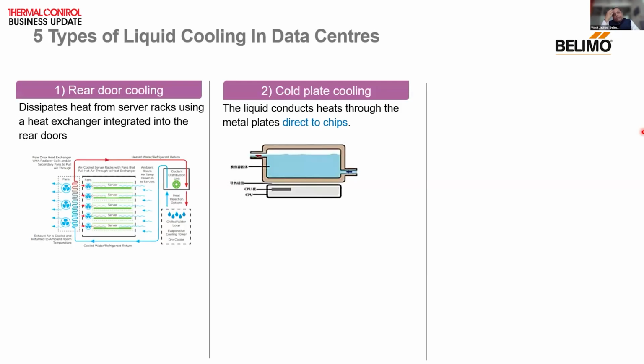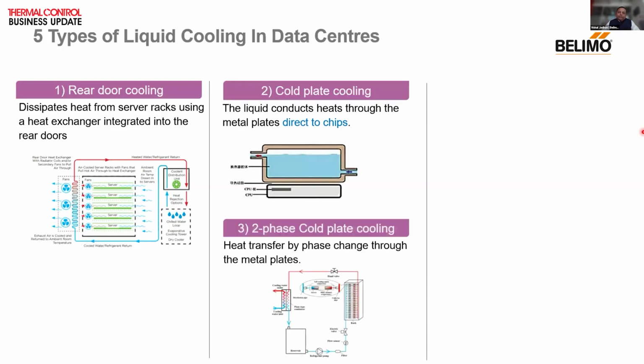In the second type, it's cold plate cooling. Cold plate cooling is nothing but liquid conduits or liquid chilled plates which are placed on the server racks. We also call it cold plate cooling or direct to chip cooling. Third type is two-phase cold plate cooling, wherein the liquid or the media changes the phase, and that's where the cooling takes place.